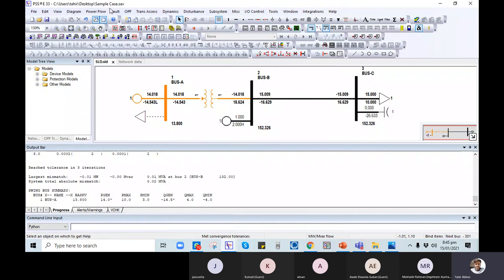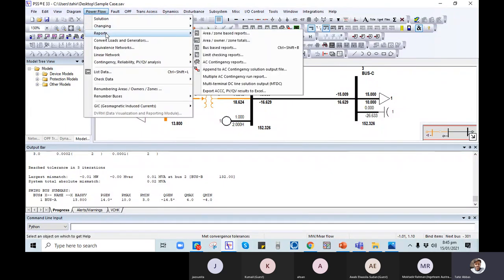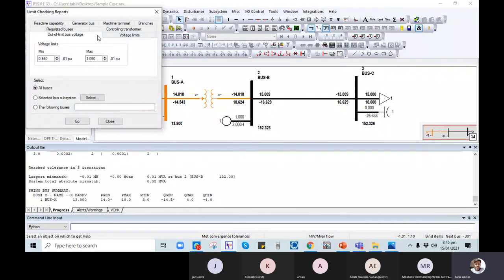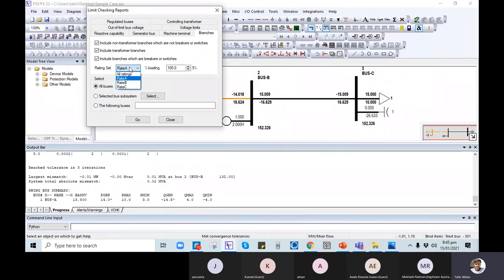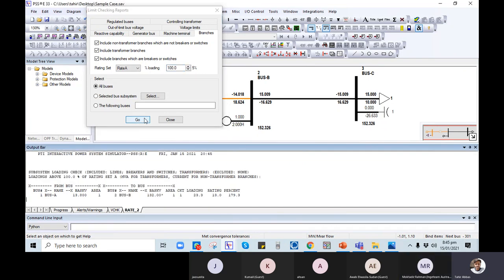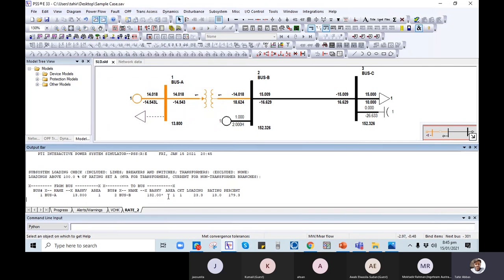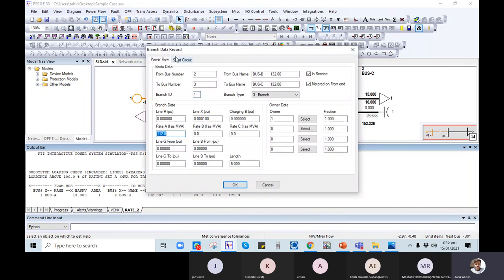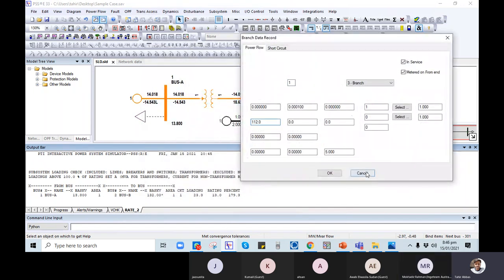Here you can see. Now go to this power flow solution and report, okay? And then go to limit checking report. Here is a branches option, branches, okay? And then here you can set the rate A, okay? And loading is 100% because under normal condition, as we have studied in the presentation. Click on okay. The report is that one circuit is overloaded. Can you see here the rate is 112, okay? I mean the percentage loading, we can see the percentage loading.